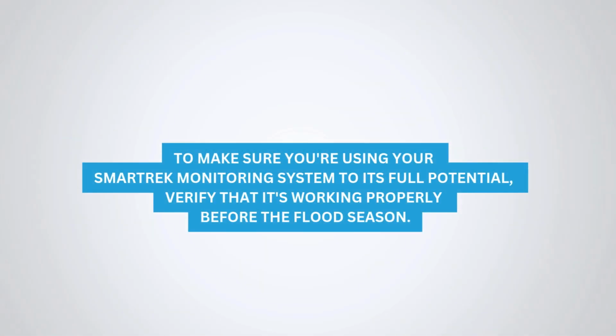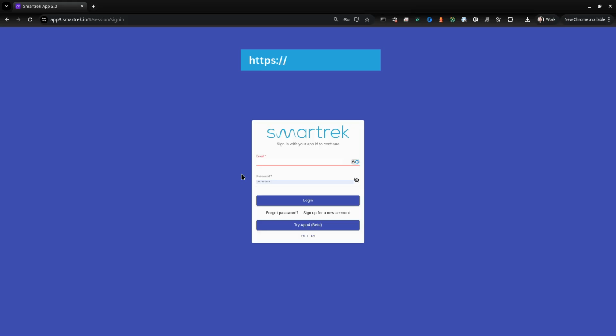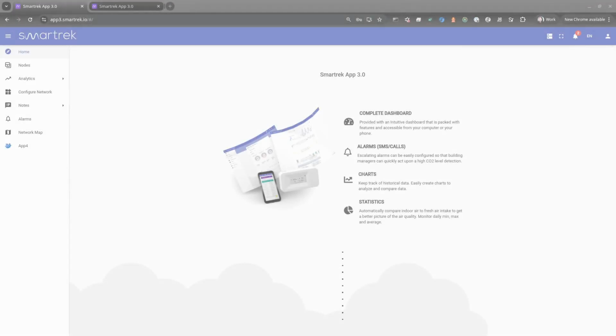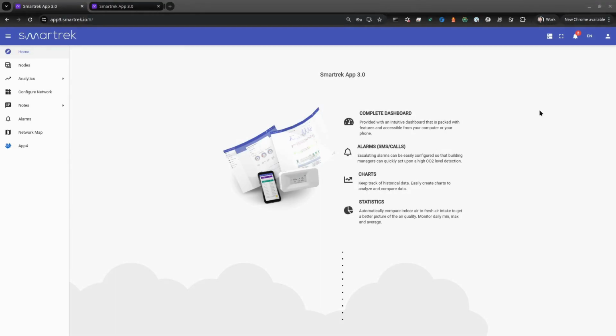To make sure you're using your Smartrek monitoring system to its full potential, verify that it's working properly before the flood season. Navigate to the page https://app3.smartrek.io. Enter your account credentials to log in. Then confirm that your gateways are communicating properly with the server. The gateways should not be highlighted in red.